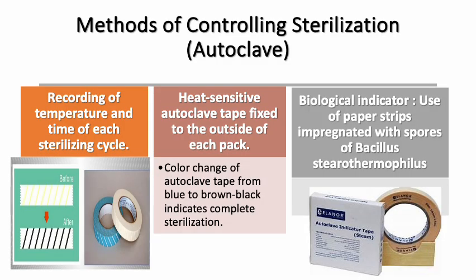So as we have discussed earlier, autoclaving is the most effective way. However, to ensure the sterility of the autoclaving process, there are different methods being employed during autoclave cycles to ensure that the conditions required for sterilization are met. For example, materials being sterilized are taped with a piece of autoclave tape. When we say autoclave tape, this is what we use to ensure that the proper temperature is achieved. Okay? And the proper sterilization is achieved. And then it is used together with the materials to be autoclaved in the chamber.